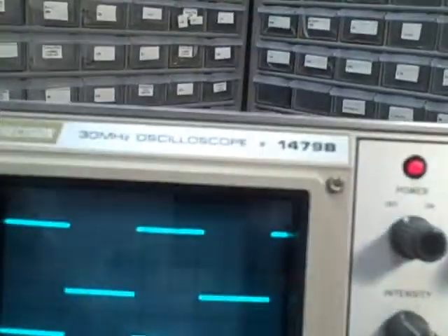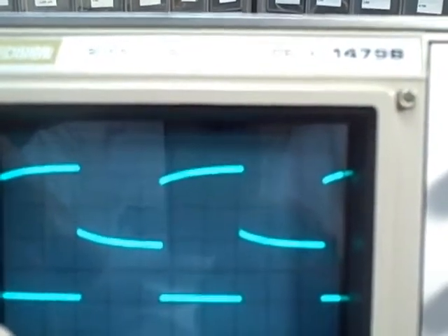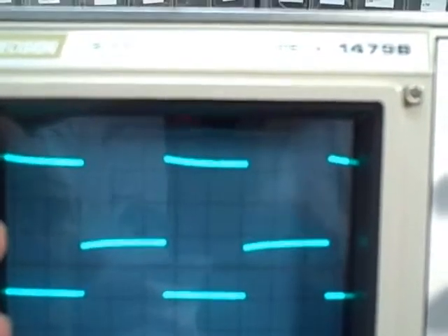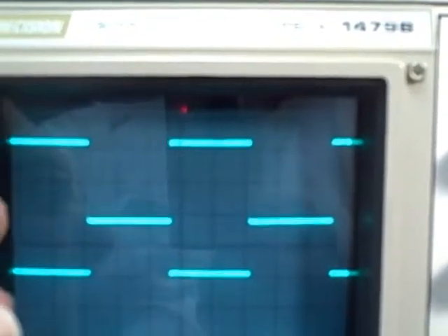Right now I'm adjusting channel 2. And you can see I've over adjusted. This would be under adjusting. And you go for the squarest waveform you can get. That looks pretty good. Let's go to channel A. And we do the same thing. Let me shift hands here so that you can see what I'm doing. Alright, I'm adjusting the probe for channel A. It's under adjusted, over adjusted, and then it's perfect square.